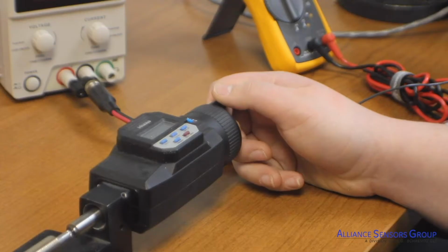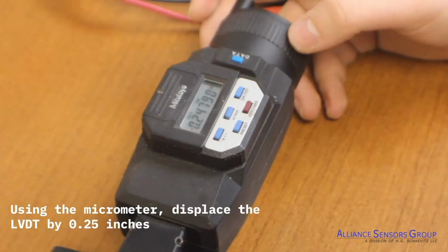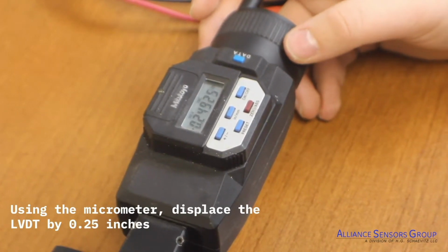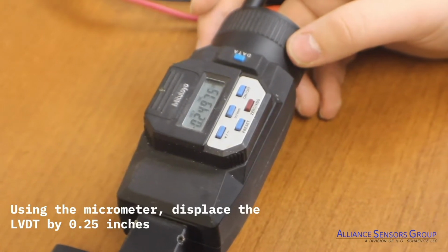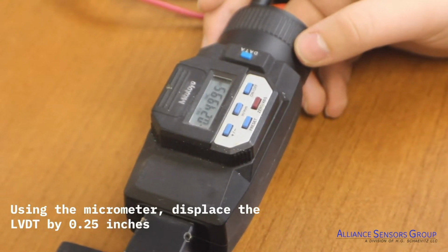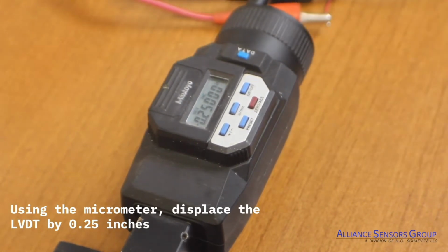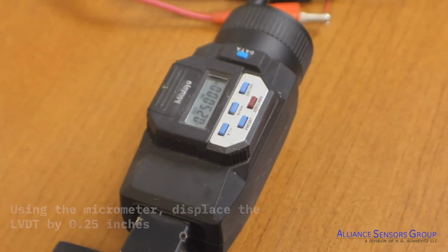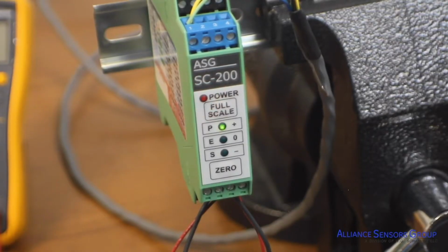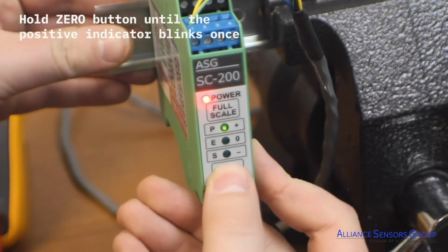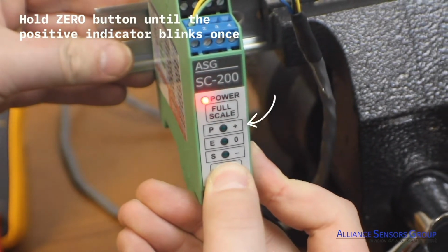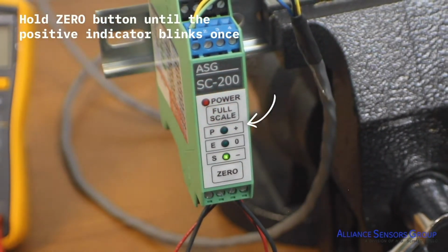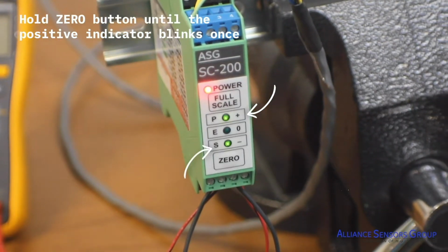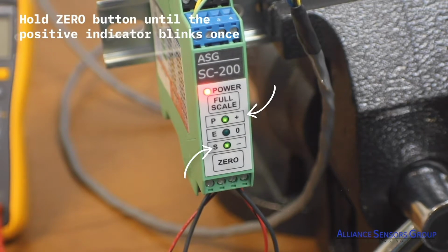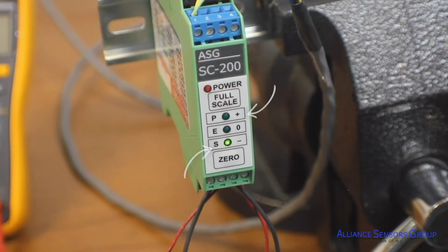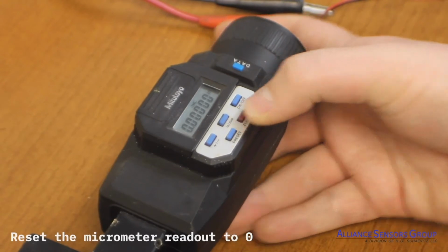Next, using the digital micrometer, displace the LVDT by minus 0.25 inches. This will take us to the negative end, or 0-inch position of the LVDT's stroke range, and will be the SC-200's 0 VDC output position. Enter the 0 point position into the SC-200 by momentarily holding the 0 button until the positive indicator blinks once. The negative indicator will now glow solid, and the positive indicator will begin to blink. This shows that we have successfully set the 0 point position. We now reset the digital micrometer readout to 0.